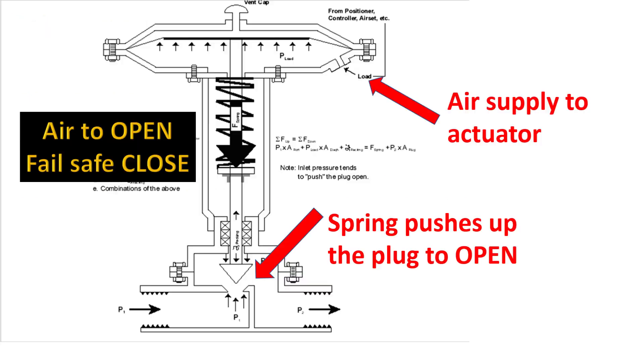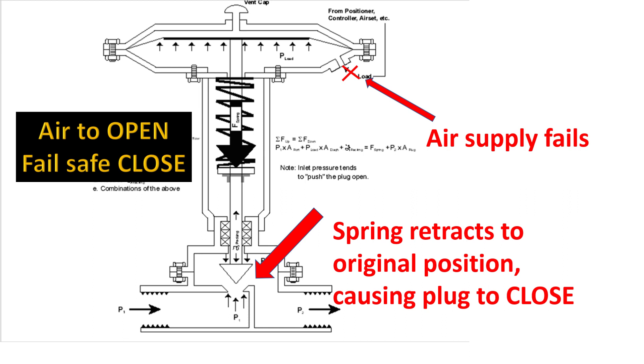You can see here this actuator has air supplied at the bottom to open the plug. When the air supply fails — as indicated here — the spring automatically retracts to its original position, causing the plug to close. You can see that when the air supply fails, the spring returns to its original position so that the plug gets closed in the control valve body.